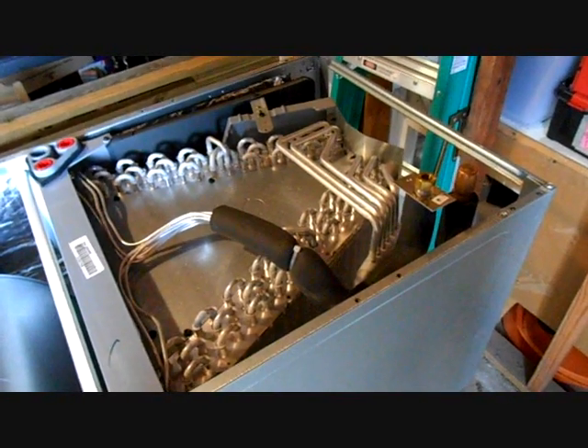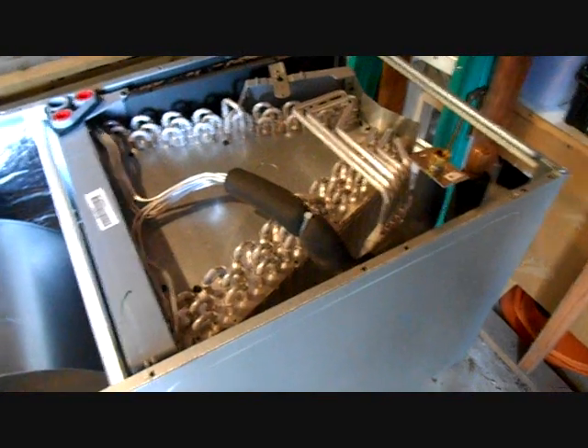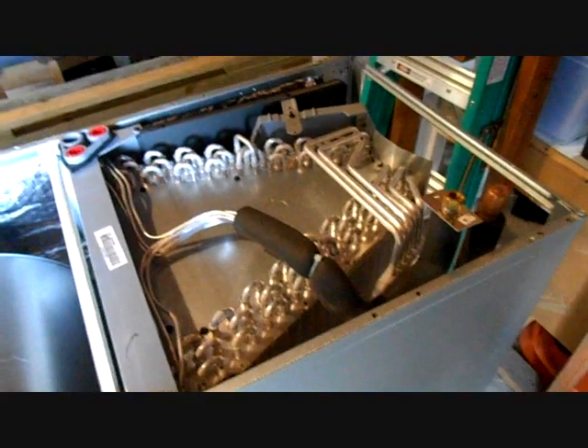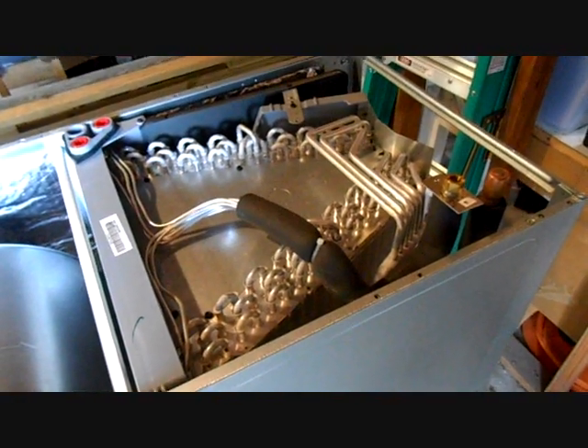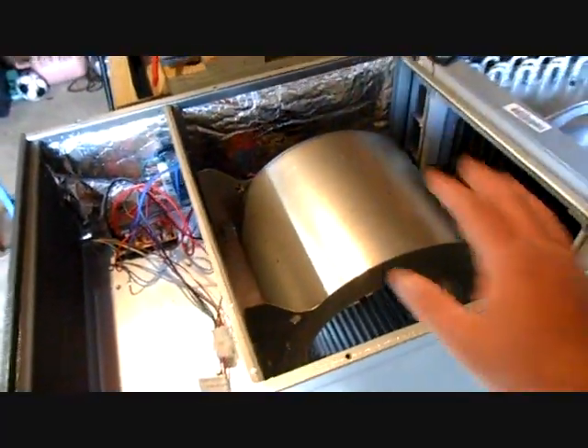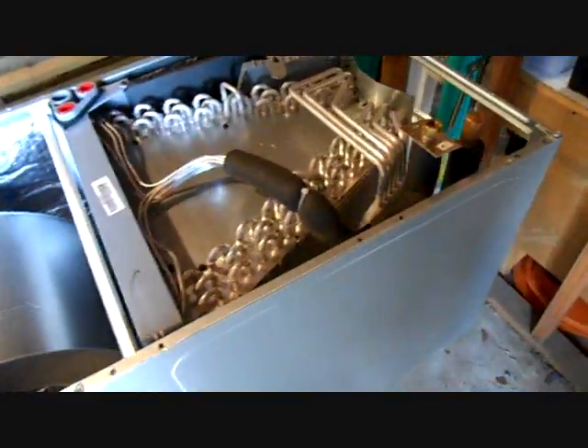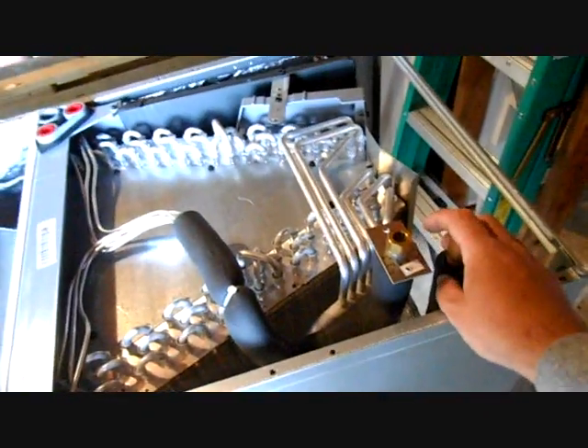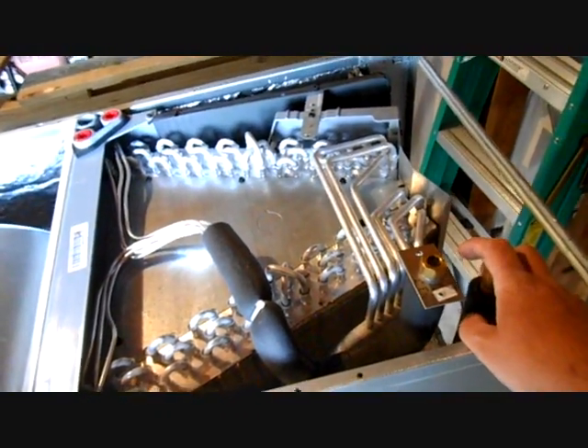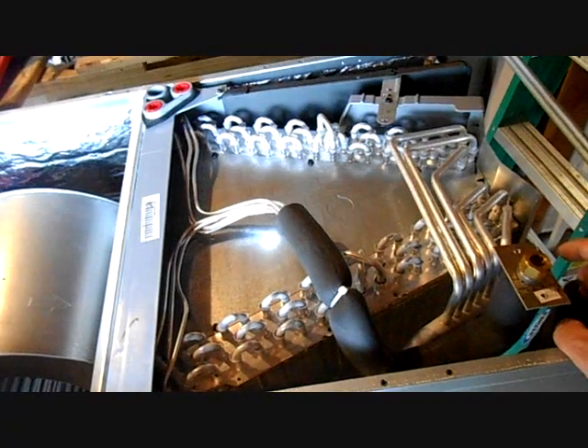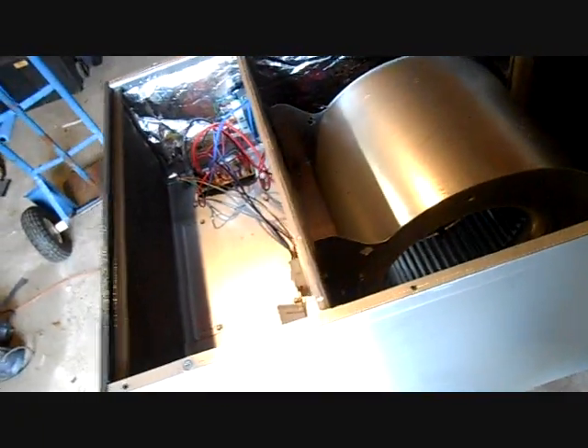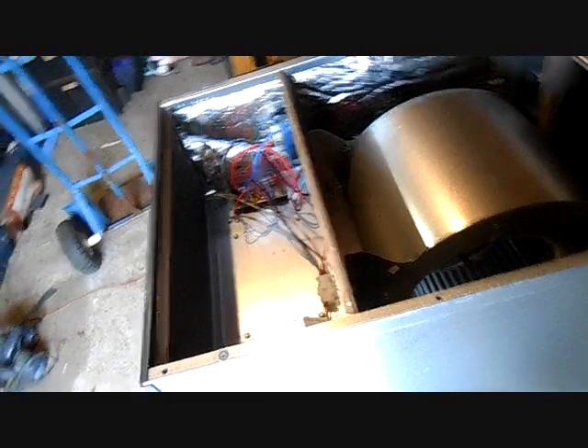It's basically the same thing as foam tape. The same as you would do with your pipes, or certain weather stripping. So I insulate the bottom of the drain pan so it won't sweat, thus keeping water off of the blower motor and out of the electrical compartment. I'll also have a freeze stat on this unit to keep it from freezing up, and a float switch to keep it from overflowing since it is down flow onto the electrical components.